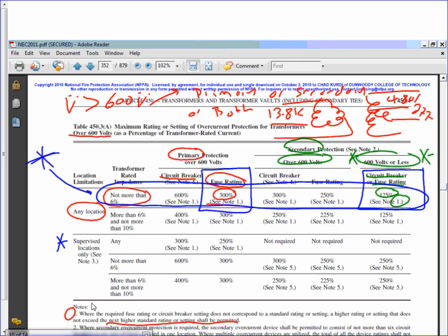Why did we go to this table, not the one before? Because the voltage on the primary side is more than 600 volt. Before we leave this topic, I will remind you guys, we go into any location, we go into the first row, the impedance is the 6%, circuit breaker gives you 600, fuses 300. I'm using fuses on the primary, so I use 300. On the secondary side, I'm using circuit breakers or fuses, doesn't matter, but the voltage is 600 volt or less, so I use 125. And both of them have note number 1 right here and right here. So you can go up.